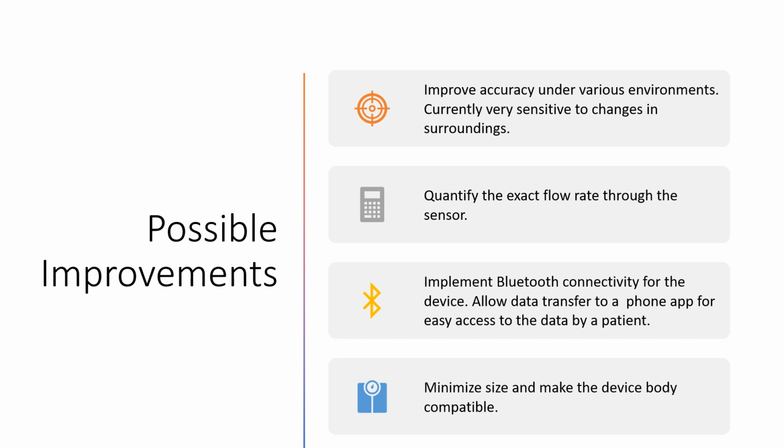And the flow rate for these baclofen pumps or implanted pumps in general is very low, so being able to detect such a low flow rate will also be slightly challenging, and therefore adapting the device in such a way that it will be able to even detect such low flows is going to be a further possible improvement. Then also implementing Bluetooth connectivity, because in the end it is going to be an implanted device, if we do continue to go down this path.